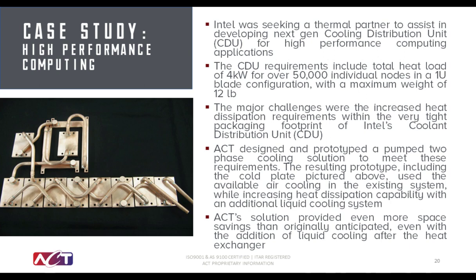Now let's talk about a case study for a high-performance computing application. In this case, the customer was Intel, and they were looking for a partner in developing a next-generation coolant distribution unit and cold plates for a high-performance computing application. The requirement was for a 4-kilowatt system, and the system had over 50,000 individual nodes, each with a one U-blade configuration. The system had a maximum weight of 12 pounds.